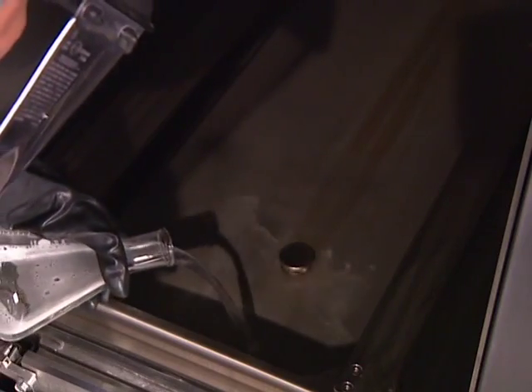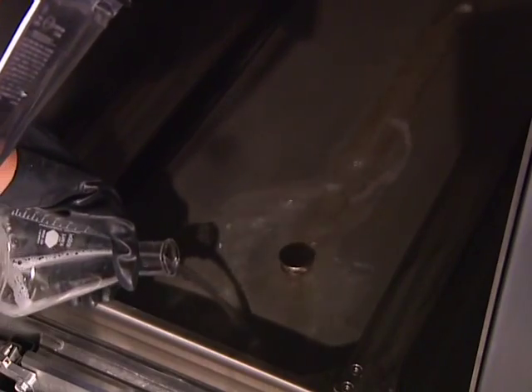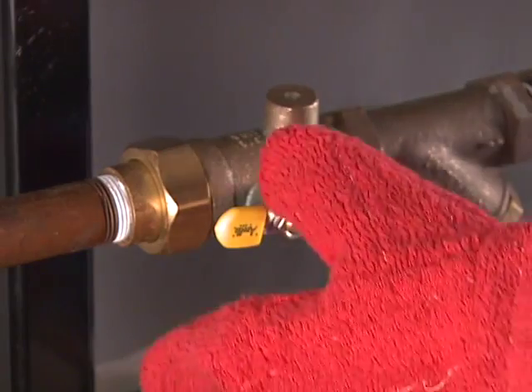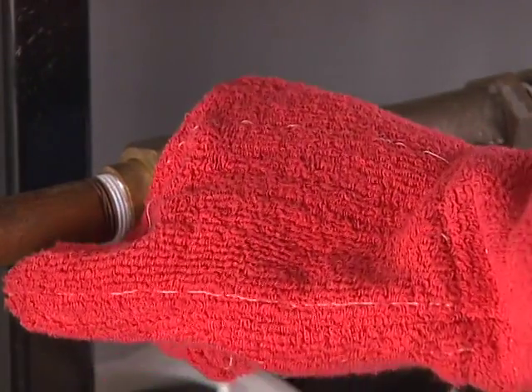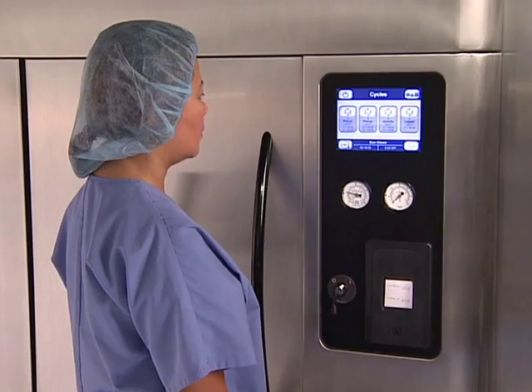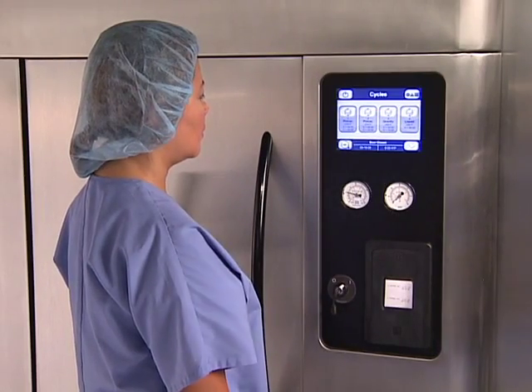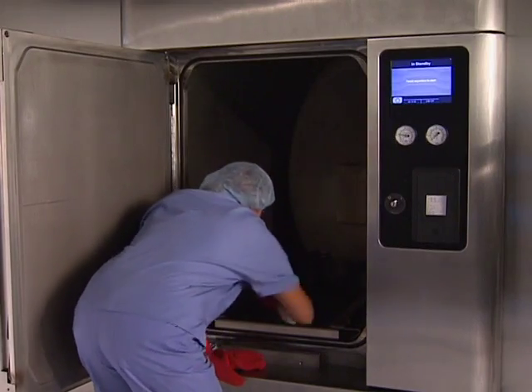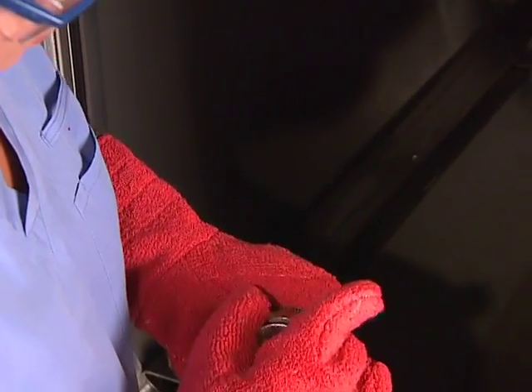Once a week, or whenever the drain line becomes clogged, you'll need to flush the chamber drain. First, turn off the steam supply valve. Wait until the jacket pressure is 0 and the chamber has cooled to room temperature. Remove the chamber drain strainer and clear the strainer as usual.